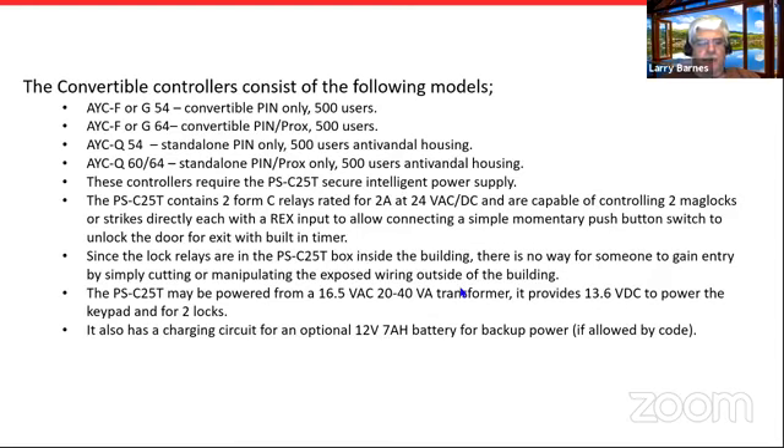The PS-C25T is where your lock relays are located. It's not weatherproof — it must be protected and mounted inside. So if someone were to pry the keypad off the wall and get to the wiring, there's nothing they can do from there to actually unlock the door. There's actually a protocol that runs back and forth — commands are sent from the keypad to the intelligent power supply to operate or release the relays.